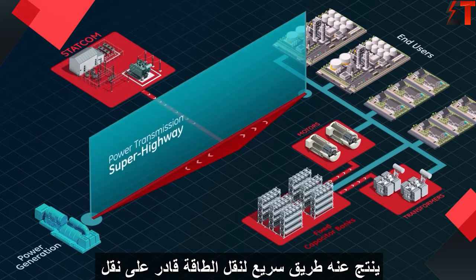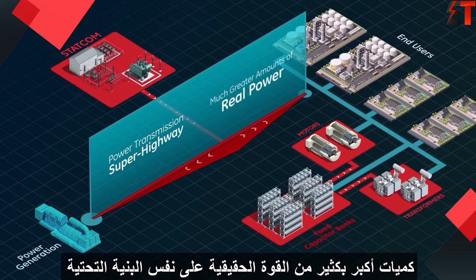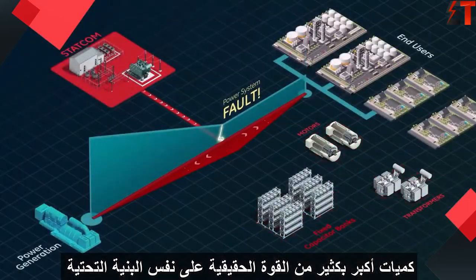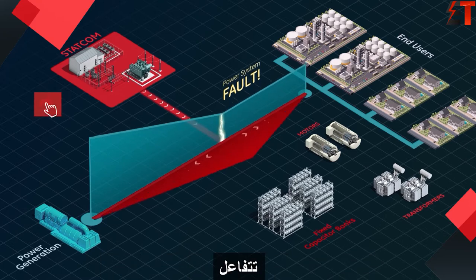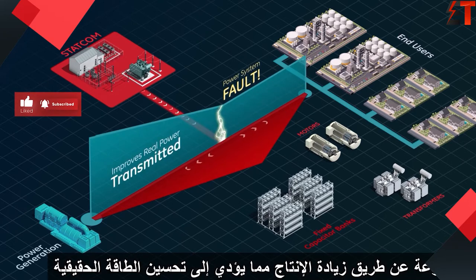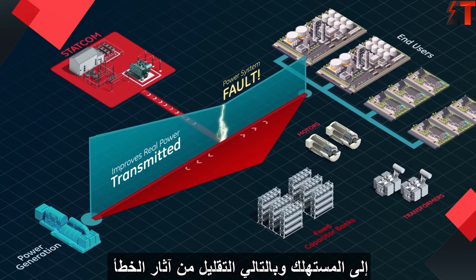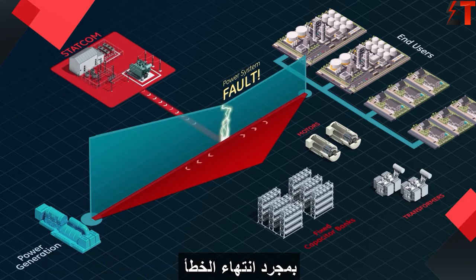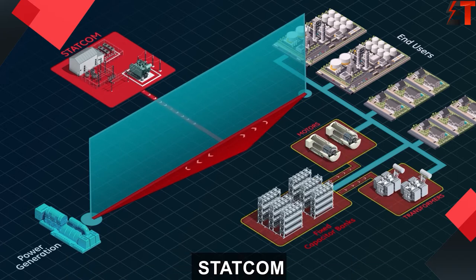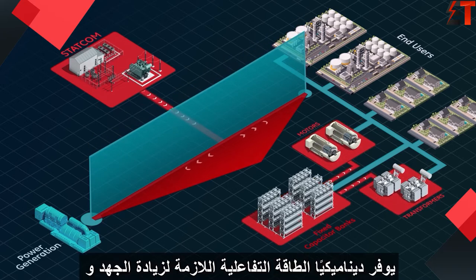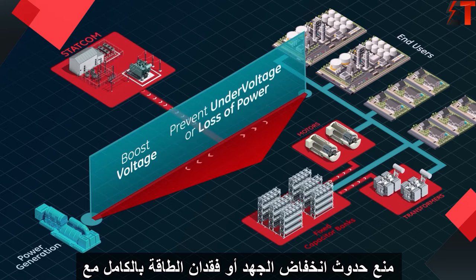This results in a power transmission superhighway capable of transmitting much greater amounts of real power over the same infrastructure. When a disturbance occurs, such as a power system fault, the STATCOM reacts rapidly by increasing output, improving the real power transmitted to the consumer and minimizing the effects of the fault. Once the fault is cleared, load reactive devices simultaneously come back online and cause significant voltage sag. The STATCOM again responds rapidly, dynamically supplying the necessary reactive power to boost voltage and prevent under-voltage conditions or complete loss of power.